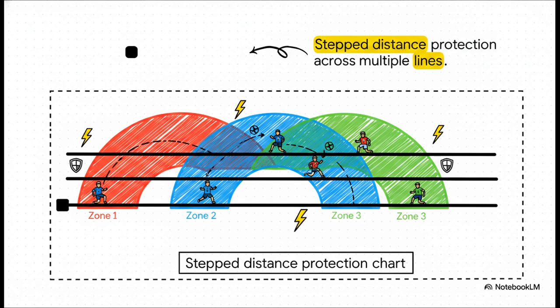Notice how the coverage doesn't just stop at the end of one line. Zone 1 acts as your primary, immediate defender. Zone 2 reaches out a bit further, providing backup. And Zone 3 reaches all the way across the adjacent lines. They cover each other's blind spots just like a perfectly coordinated sports team.